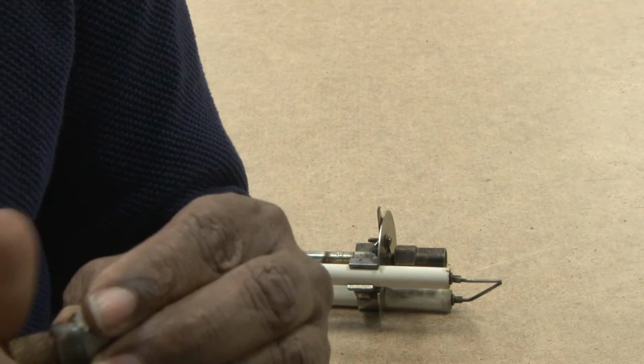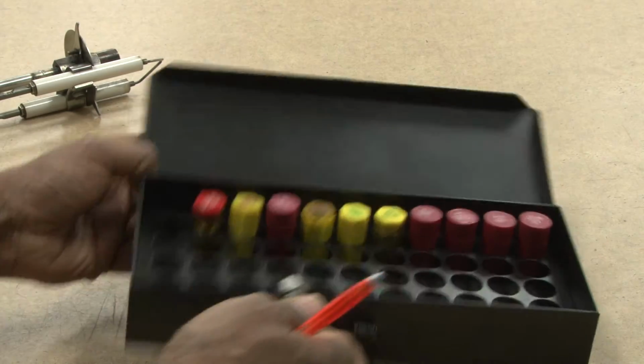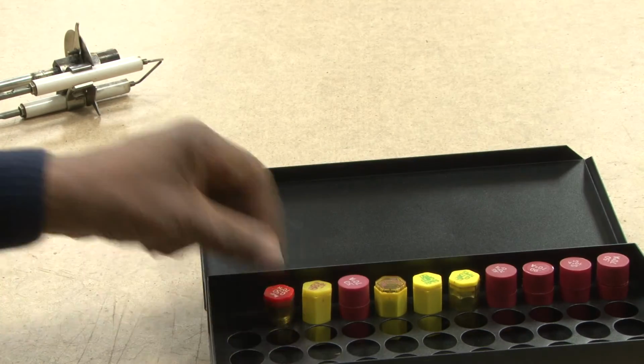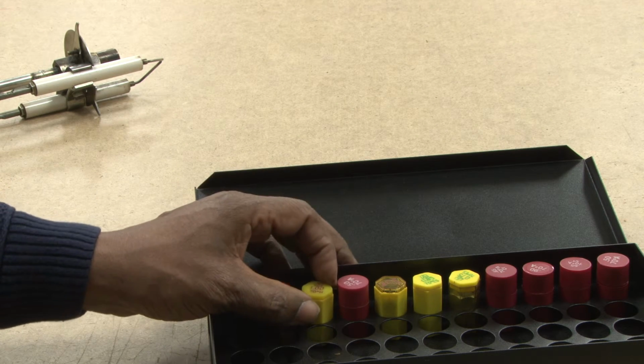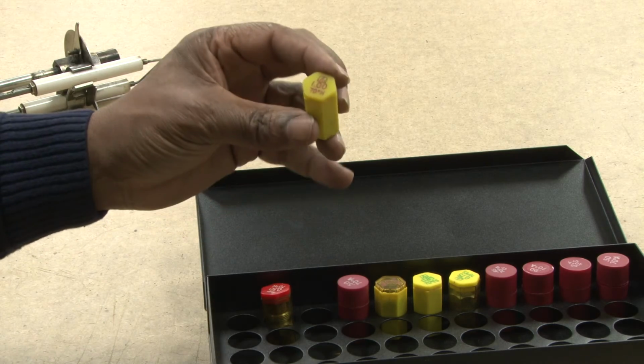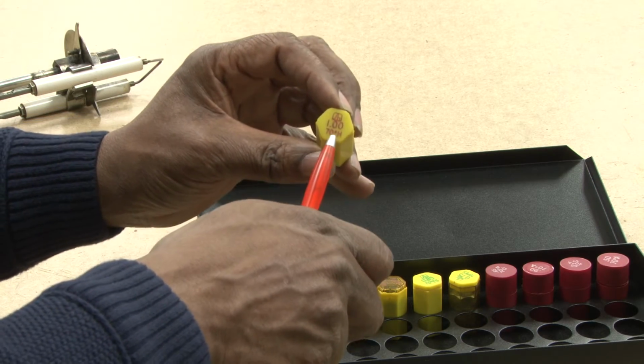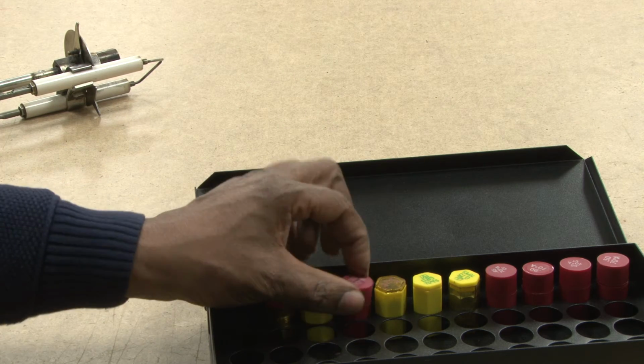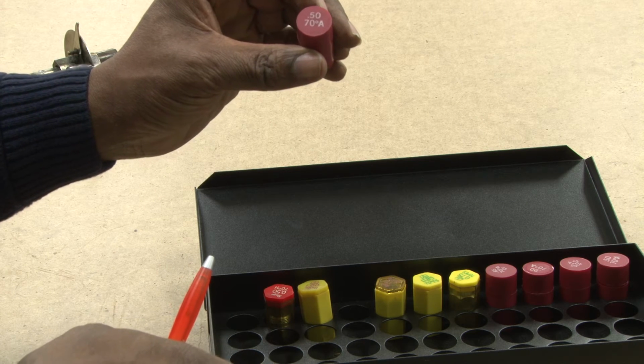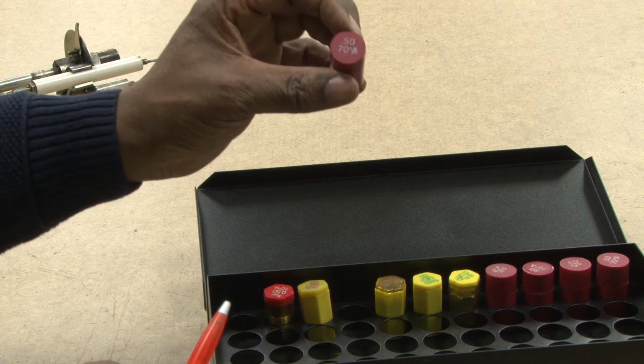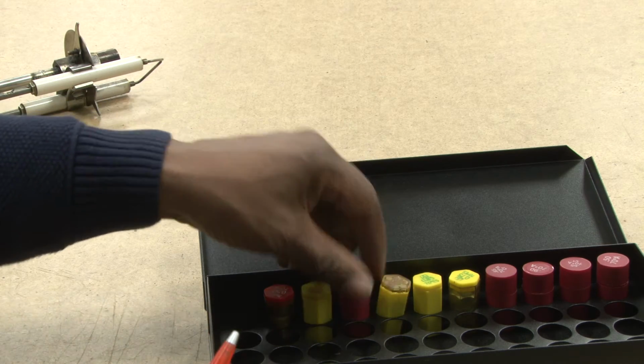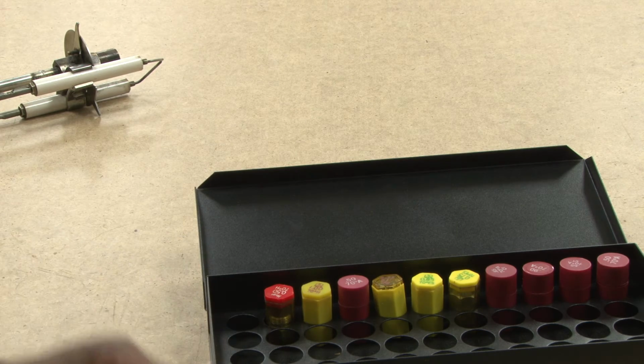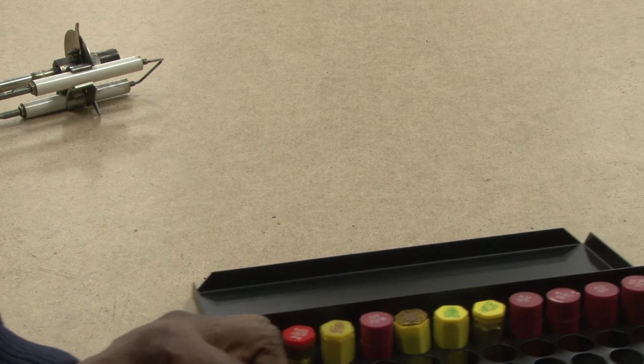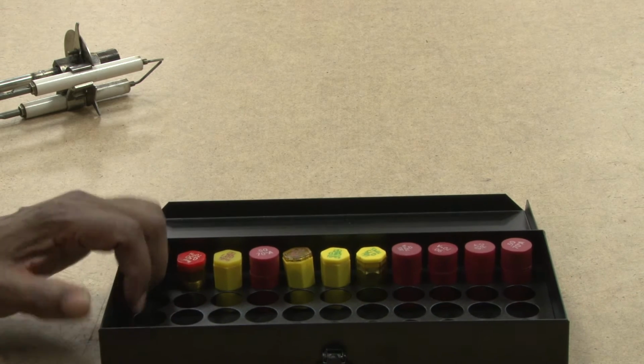So they do sell kits for oil nozzles. It would come in a kit like this, with many nozzles in it, and it will specify the GPH, gallons per hour. It will tell you what type of pattern, such as this one. It's a 70-degree hollow nozzle. This is a 0.5 gallons per hour. But anyway, they come out with many different types of nozzles. So a technician will keep one of these on his truck if he deals with a lot of oil burners in his career. A couple other components we want to look at.